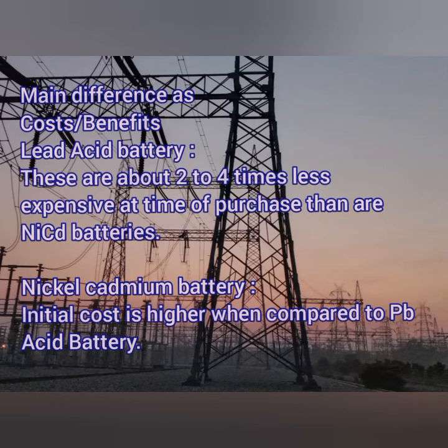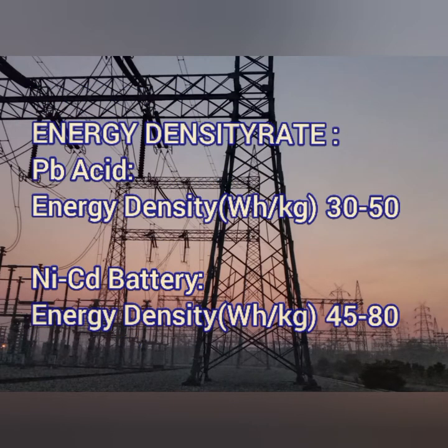Next is energy density — the amount of energy that can be stored in a cell. In lead acid batteries, the energy density is 30 to 50 watt-hours per kilogram, which is not particularly high. In nickel cadmium, the energy density is 45 to 80 watt-hours per kilogram, which is better than lead acid.